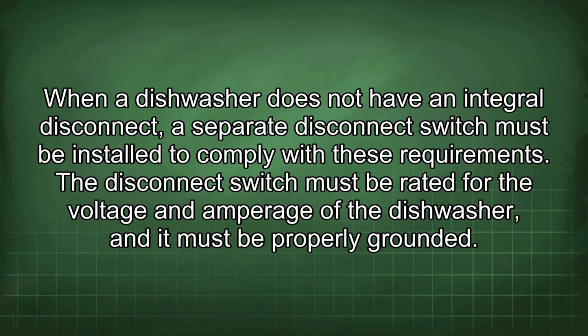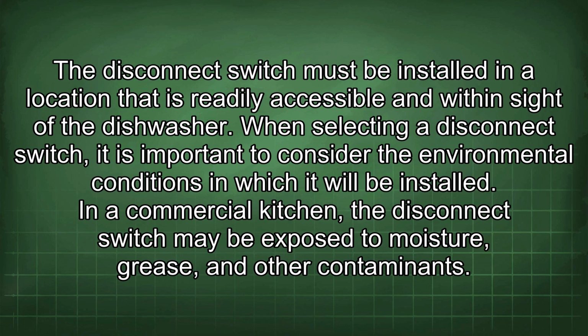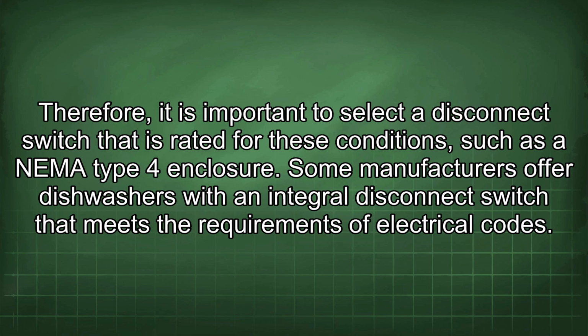When a dishwasher does not have an integral disconnect, a separate disconnect switch must be installed to comply with these requirements. The disconnect switch must be rated for the voltage and amperage of the dishwasher, and it must be properly grounded. The disconnect switch must be installed in a location that is readily accessible and within sight of the dishwasher. When selecting a disconnect switch, it is important to consider the environmental conditions in which it will be installed. In a commercial kitchen, the disconnect switch may be exposed to moisture, grease, and other contaminants. Therefore, it is important to select a disconnect switch that is rated for these conditions, such as the NEMA Type 4 enclosure.